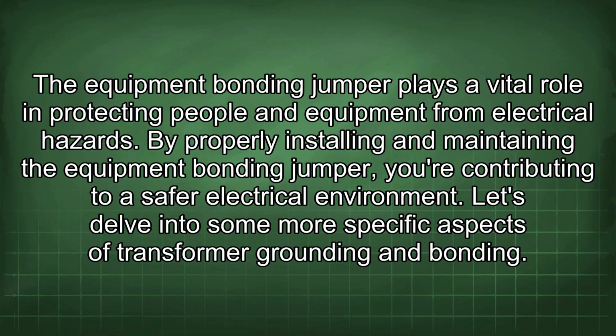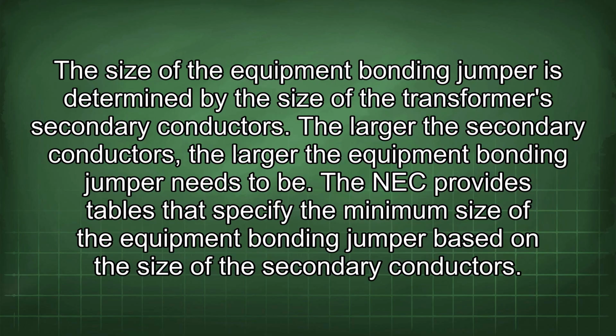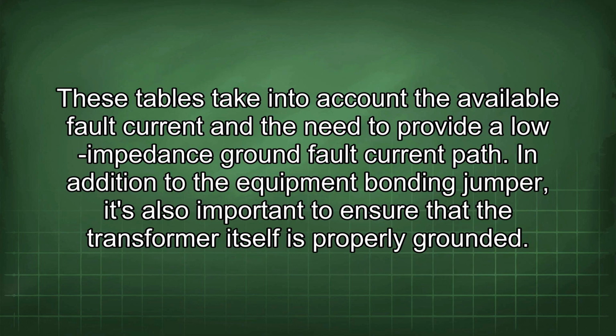Let's delve into some more specific aspects of transformer grounding and bonding. The size of the equipment bonding jumper is determined by the size of the transformer's secondary conductors. The larger the secondary conductors, the larger the equipment bonding jumper needs to be. The NEC provides tables that specify the minimum size of the equipment bonding jumper based on the size of the secondary conductors. These tables take into account the available fault current and the need to provide a low impedance ground fault current path. In addition to the equipment bonding jumper, it's also important to ensure that the transformer itself is properly grounded.